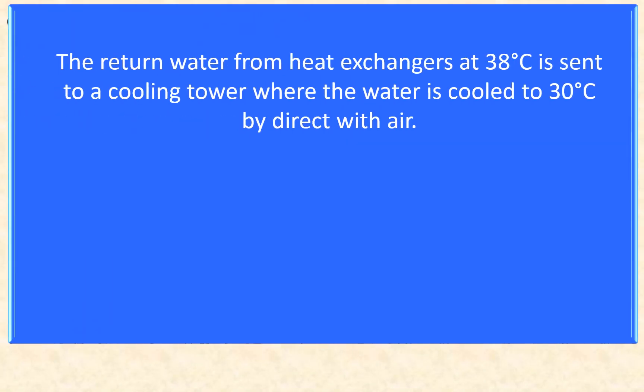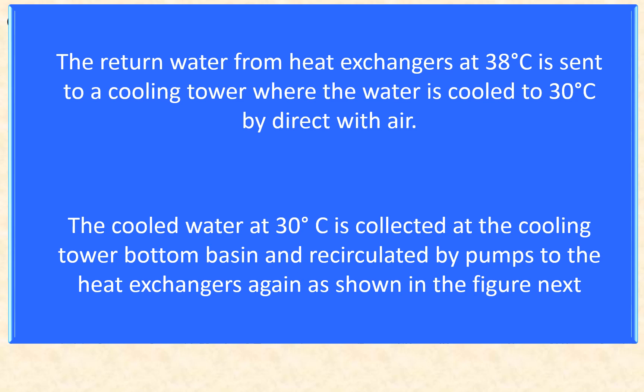The return water from the heat exchangers at 38°C is sent to the cooling tower, where the water is cooled to 30°C by direct contact with air. The cooled water at 30°C is collected at the cooling tower bottom basin and recirculated by pumps to the heat exchangers again.